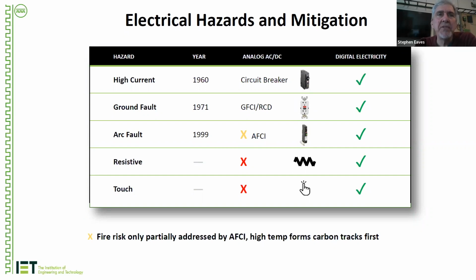But there are two other very important faults that haven't been addressed by traditional electricity formats. One of them is what's called a resistive fault, and the other is touch fault. A resistive fault is if you have a poor connection, or what's called a glowing fault in the circuit, that can reach pretty high levels of power and cause a fire in the system.